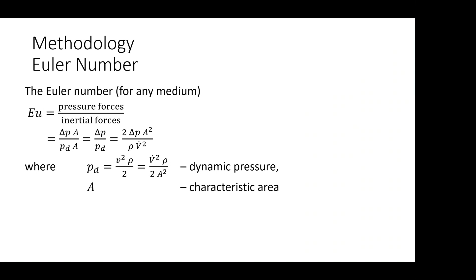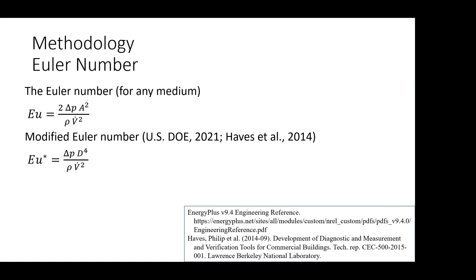We didn't create this method ourselves — we're implementing an approach invented by other people into the Buildings library. The authors used a modified Euler number, removing all the constants, so we end up with a dependency on pressure, diameter, density, and flow rate. They showed that for different types of pumps and fans, different sizes, and different operational regions, the measured data all follow this correlation curve very well.